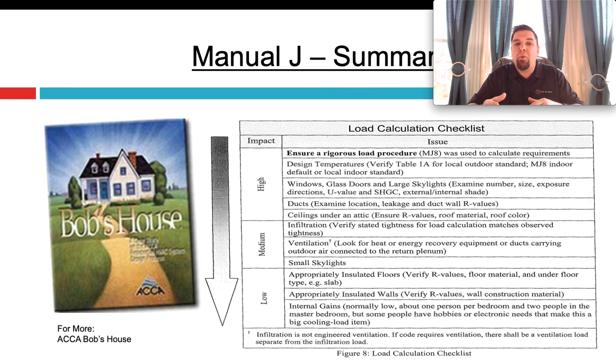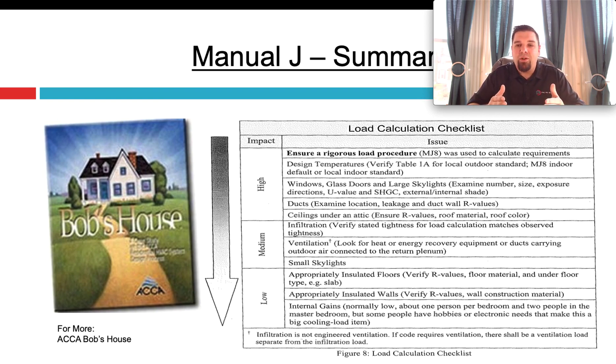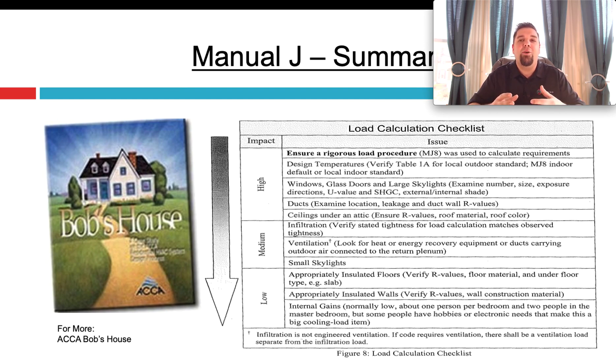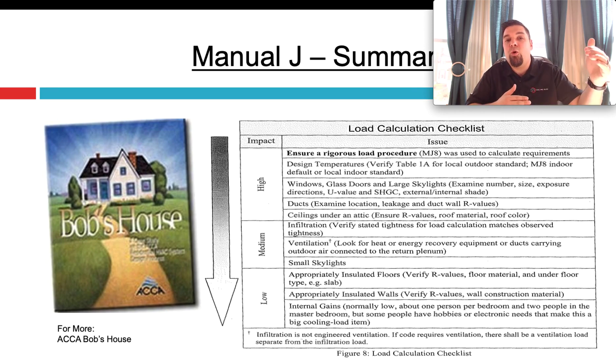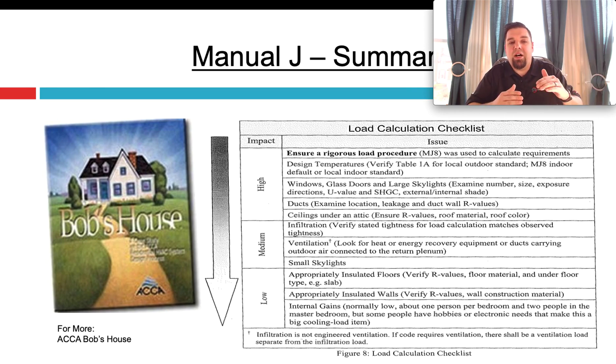Things like appropriately insulated floors to unconditioned basements, or if you're off a little bit in the R-value of the wall — say R19 versus R21 — or maybe you missed one or two large plants in the internal gains: these things are not going to impact the load as much as you would think. It's not going to change the size of the equipment like those first four things. So spend your time on those things at the top of this chart.